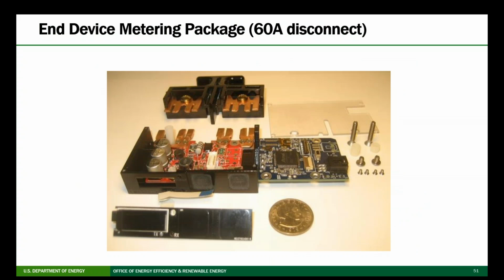I'm just wrapping up. We always talk about end-use measurement devices. Some people recognize the brass thing with the T-handle in the back—that's a shorting block of a 60 amp air conditioning disconnect. This is a meter that fits into that disconnect. With the right radio, whether Wi-Fi, Bluetooth, or whatever, you can take the shorting block out of the disconnect and put the meter directly into the hole. So this is just one of those applications. And with that, that is my presentation.